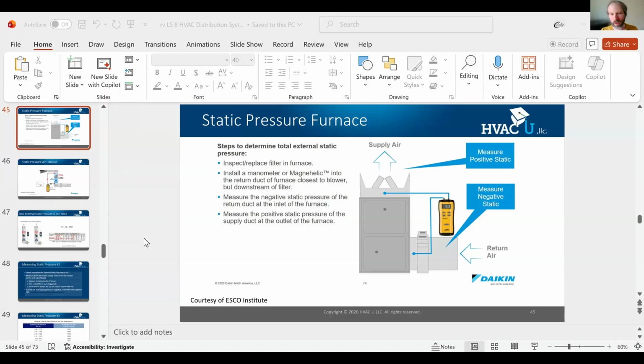So if you're testing after the filter, do you lose that, or is that somehow still in there? It depends on what you're testing static pressure for. In the context of this presentation, we were using it to get a reference point so that we can look up a chart and get airflow. The external static pressure still accommodates the pressure of the filter. So you're measuring external static pressure if you make a filter replacement.